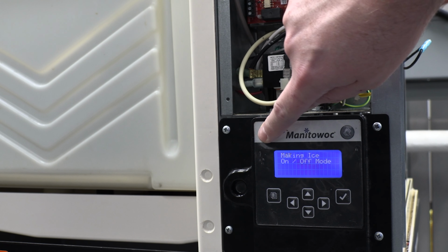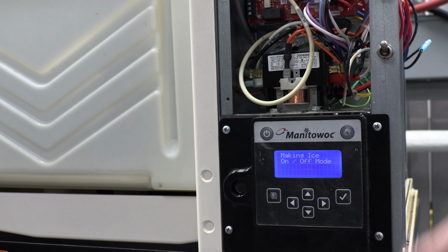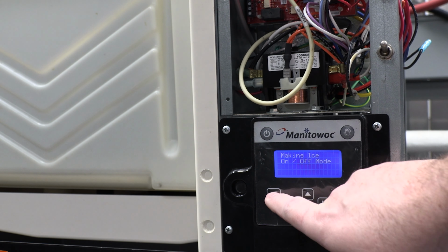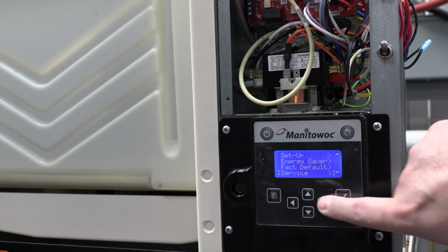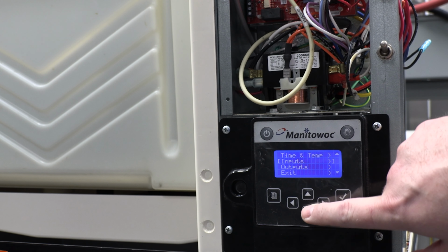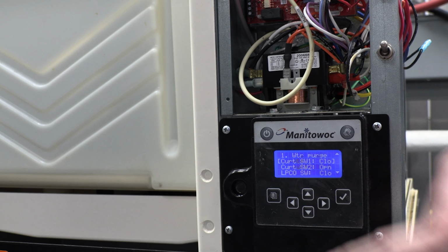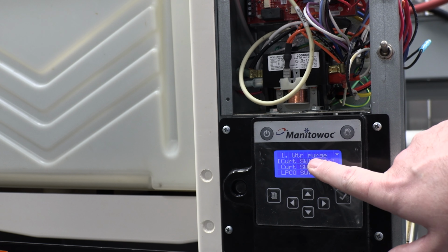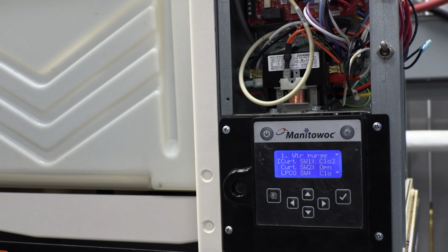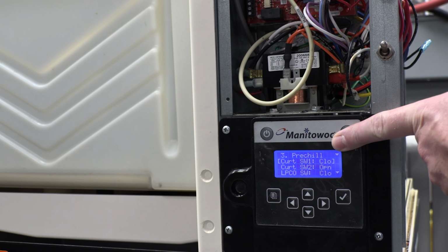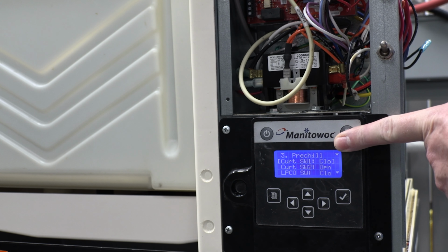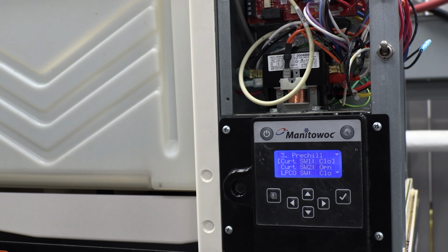So I'm going to power on the machine. See, it says making ice. We hear the control board clicking. We're going to start in our service menu here. We're going to go to real-time data. And let's just look at inputs for a minute. You see we're in water purge. Okay, the machine is now in a pre-chill mode and is filling with water. And you see we went right from pre-chill into a harvest. This is usually the complaint that we get.